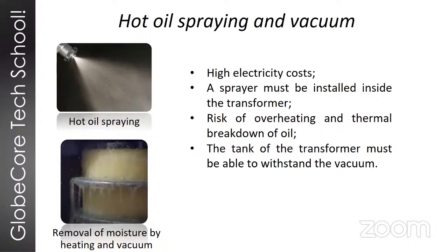And also it's sprayed over the windings through the nozzles. So when a certain temperature is reached, the oil is drained and vacuum is applied to the transformer tank. So in one such cycle, the insulation is heated, moisture evaporates, and water vapor is removed from the tank by vacuum pumps. And these cycles are repeated until we achieve the required low moisture content in solid insulation.